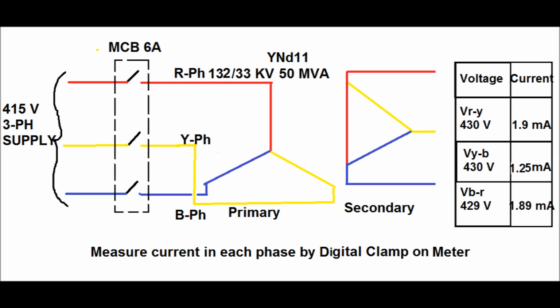phase is 1.9 milliampere. The voltage between Y and B phase is 430 volt, and the current drawn from the yellow phase is 1.25 milliampere. The voltage between blue and red phase is 429 volt, and the current drawn from the blue phase is 1.89 milliampere. Here you can see the current in red phase and blue phase is almost the same, but the yellow phase is lower compared to the red and blue phase. Now we will explain the reason for this variation of the current.